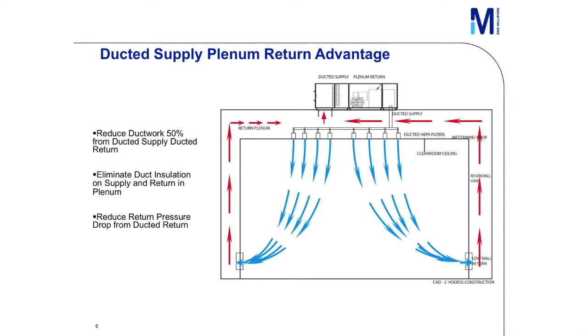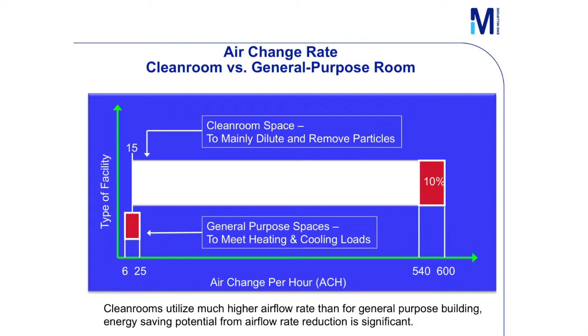That also really works in your favor because it reduces the pressure drop from putting it through a small ductwork versus that plenum. This is the key slide here, and I don't really want to make a science project out of it, but the room we're sitting in right now is probably about 6 to 25 air changes an hour. Clean rooms, anywhere from 500 to 600 air changes an hour. So if you can run that clean room close to what we're in right now, you're going to save a tremendous amount of energy, and I'll show you what we did.